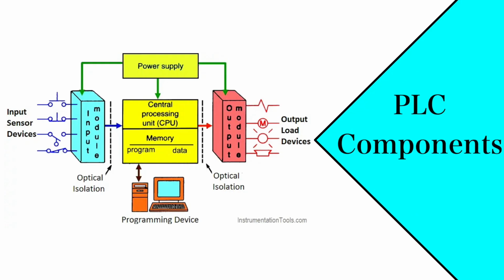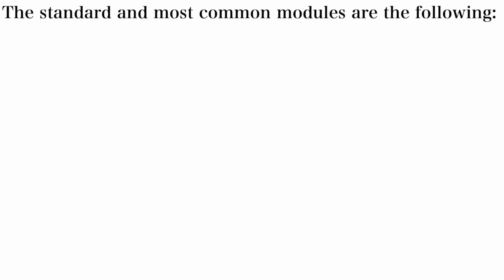Now let's talk about the programmable logic controllers' input output components. The PLC input output components are very crucial for interfacing between the industrial automation systems, input output devices and the microprocessor. So you can say it is the main interfacing link between the industrial automation system, input output devices and the microprocessor. It mainly executes a control logic. These modules are essential after the microprocessor but can vary in form, but typically include a power source, electronic circuits for signal conversion, a terminal block for cable connections and a mounting mechanism for its safety. The most standard and commonly used input output modules are the following.